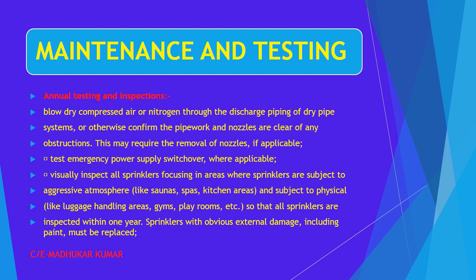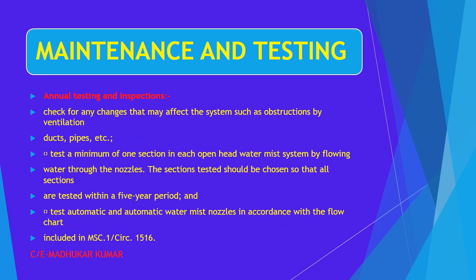Okay, visually inspect all sprinklers, focusing on the areas where sprinklers are subjected to an aggressive atmosphere. Okay, so all the sprinklers' inspection must be done. Okay, all sprinklers are inspected within a 1 year system. We have to make a program so that the sprinkler heads are visually inspected for the proper functioning of that. The sprinklers with obvious external damage, including paint, must be replaced. Suppose it is being painted or any external damage you are observing by the visual part of it, so it must be replaced. Check for any changes that affect the system, such as obstructions, ducts, pipes. If these things are there, they must be removed.